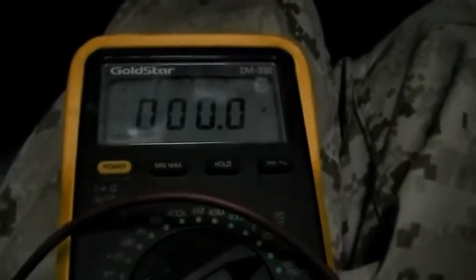100 volts still. And I called Edison and they said, oh, low voltage problem, that's not a priority, 5 business days. And I said, well, wherever the high resistance point is, it's gonna burn and be a total blackout long before then. I looked out at the street and all the street lights are really dim and flickering. We could go out there. There's a street light.